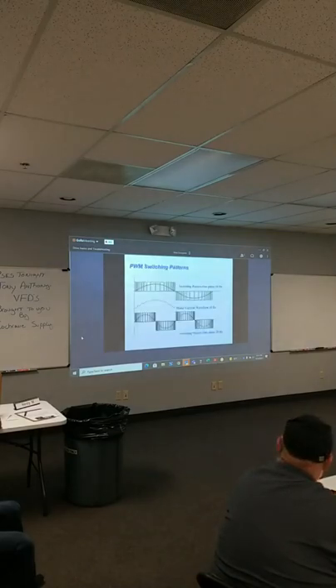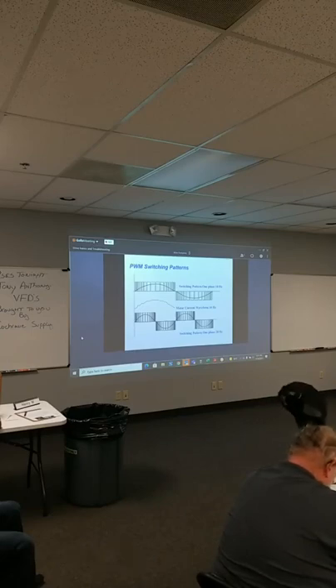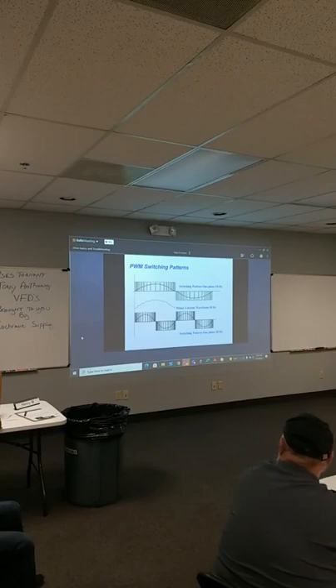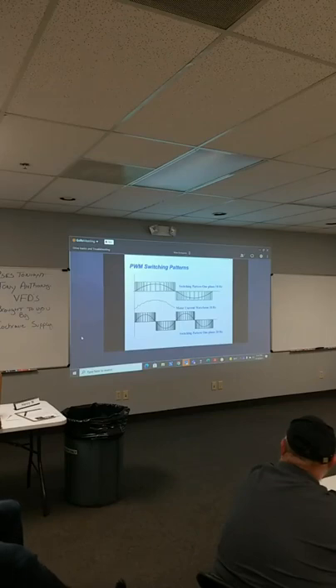Carrier frequency, we talked about that. Well, first, this would be the pulsing pattern. So if you're running 10 hertz, it might be one set of patterns. Running 20 hertz, you'd have double the pulses to create it. Running 60 hertz, we'd have, you know, six times the pulses to create it. And the carrier frequency we're talking about is how fast we turn those switches on and off.